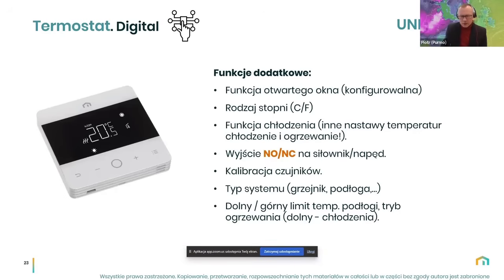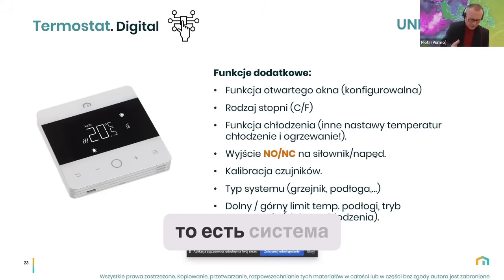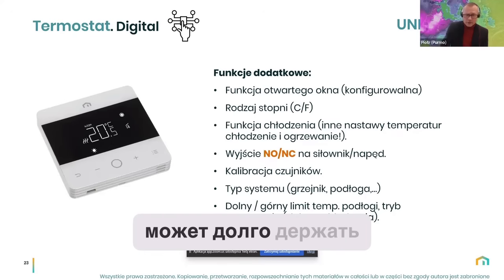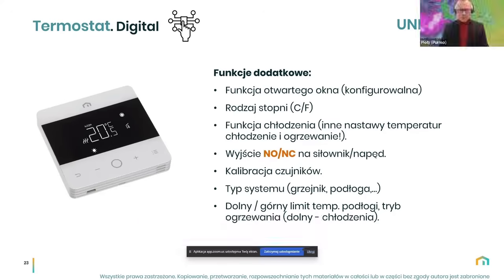The same logic works in the opposite direction for a cooling system. If the temperature changes rapidly, more than expected and without influence from the system, while the system wants to provide heating and the temperature goes down rapidly, it assumes the window is open and stops heating so as not to heat an open window. But after some time - I think this is 2 hours - it starts heating again because it cannot let the temperature stay reduced for too long.